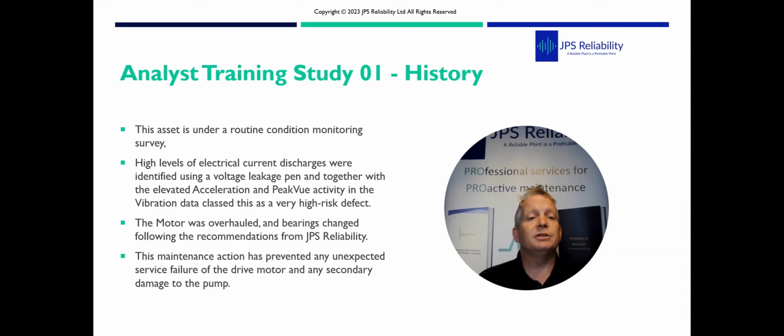We've monitored it for a while, and we had a defect, and we used an additional tool, a shaft voltage pen, to confirm what the vibration was saying. They only have annual shuts, so we ran the risk so much that at the next shut we said this is too high risk, the bearing needs to be pulled, and this is a case study to show you the vibration data and how we did it. Next we're going to jump into the vibration software, and I'm going to show you a bit of the analysis and how we detected what the defect was.